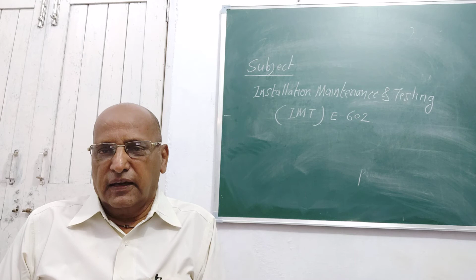Some transformers are provided with wheels and some with nut bolts. If it is provided with wheels, then you have to put a wheel lock arrangement on the channel, so that the transformer is not disturbed and cannot be shifted from one place to another. It is rigidly tied with the wheel. Wheels are provided only for the purpose of transportation, and if wheels are not provided, then nut bolts are provided for the holes in the frame of the base of the transformer.